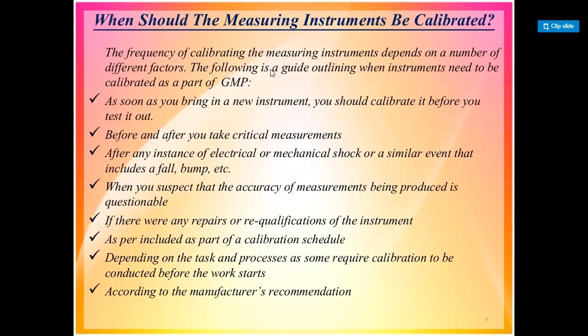So, importance of regular calibration. What is the importance? Why is regular calibration required? Calibration is responsible for defining the accuracy of any measurement and its quality that is recorded by any instrument. When you start working with any instrument, it must be calibrated well, thus assuring you of accurate results. However, over a period of time, you will start observing a drift. Calibration minimizes such uncertainties by assuring the accuracy of test equipment.